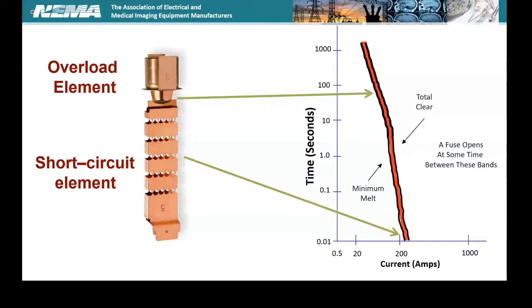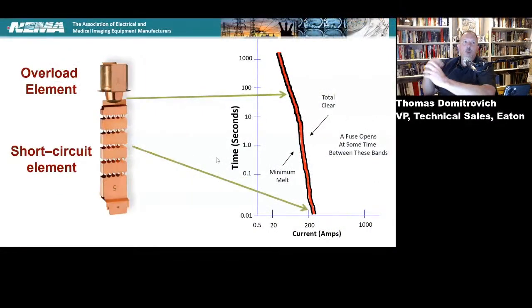Yeah. So what you're seeing here is what's inside the tube, so to speak, and all of those pinch points that you see on the bottom portion of that element, that's what takes care of the short circuit. So what you're not seeing is that there's sand all the way around that element. And what happens is when the fault current is large enough that it flows through and blows all of those little pinch points, and it heats that sand up. And we know what happens when you heat sand up. It creates what they call fulgurite. I don't mean to be vulgar with you, but it turns that into fulgurite, which is a glass, a very good insulator. So that's your short circuit protection, but it takes a lot of current to blow those pinch points.